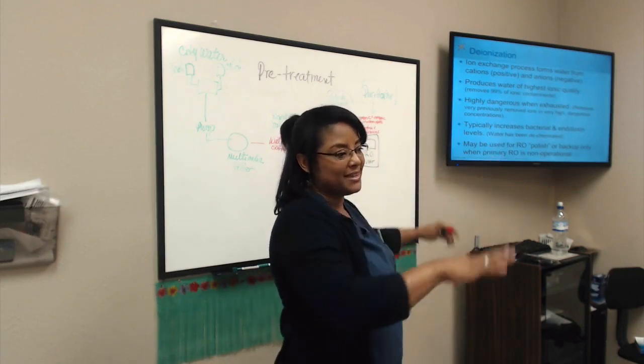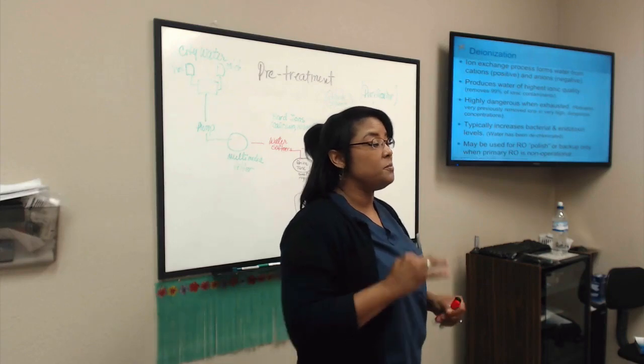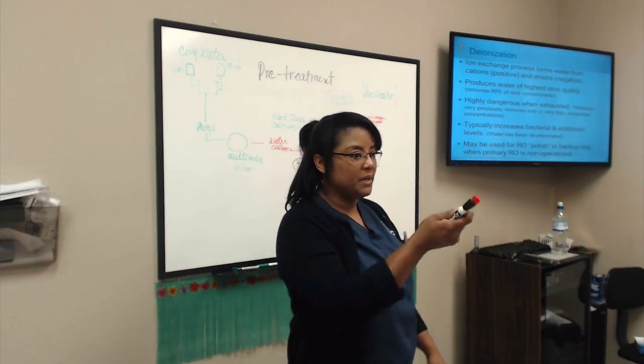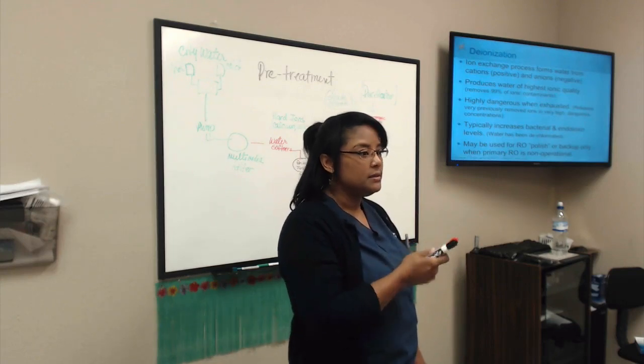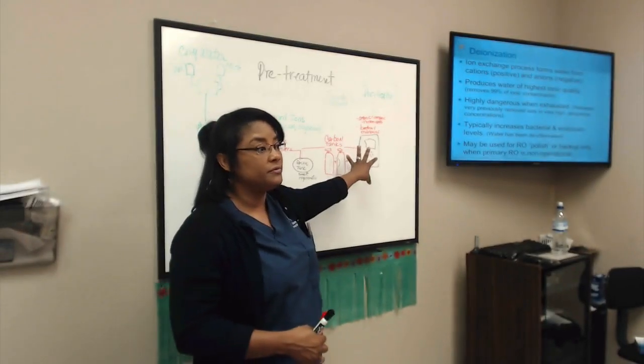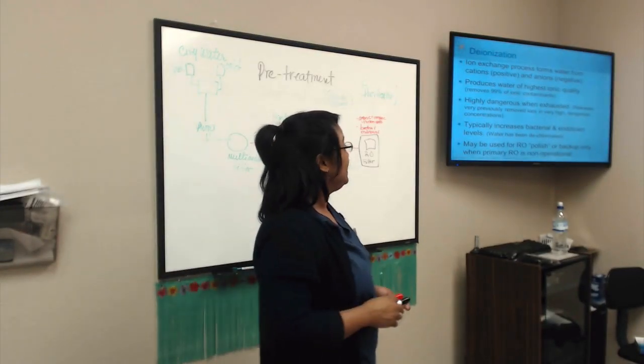That is the dangerous part. So if we go more than 24 hours with the same DI tank, we're putting the patients at risk of pushing all these things that we removed first into their system, okay?